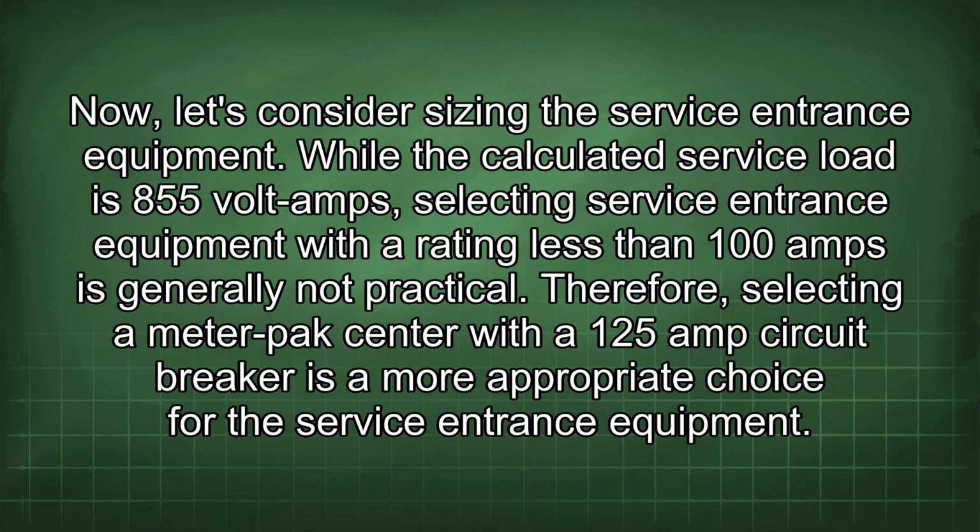While the calculated service load is 855 volt amps, selecting service entrance equipment with a rating less than 100 amps is generally not practical. Therefore, selecting a meter pack center with a 125 amp circuit breaker is a more appropriate choice for the service entrance equipment.